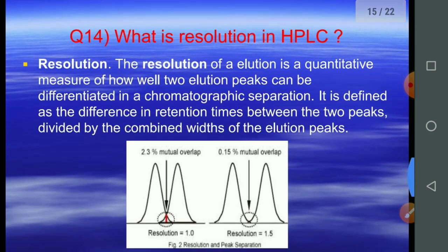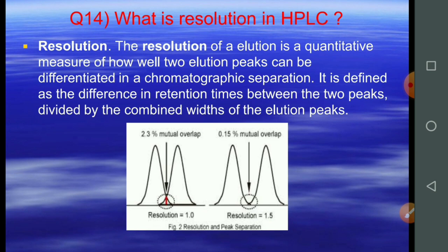Question number fourteen: what is resolution in HPLC? This is the most important system suitability parameter of HPLC. Resolution is the quantitative measure of how well two elution peaks can be differentiated in a chromatographic separation. It is defined as the difference between the two peaks divided by the combined width of the elution peaks.